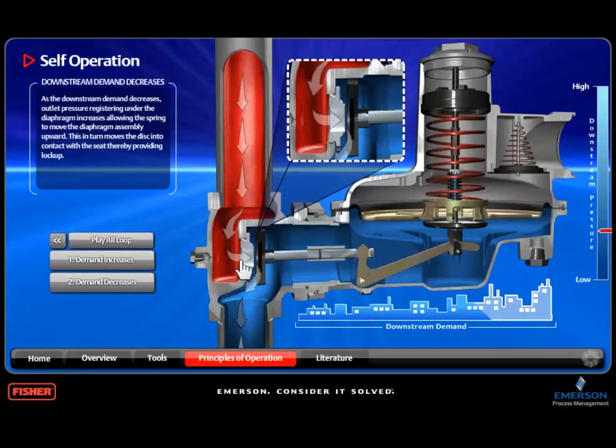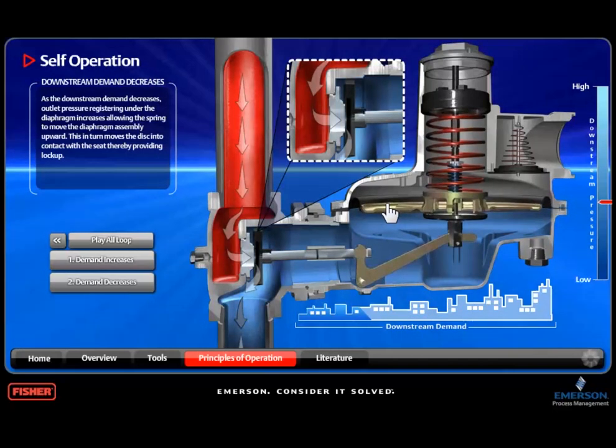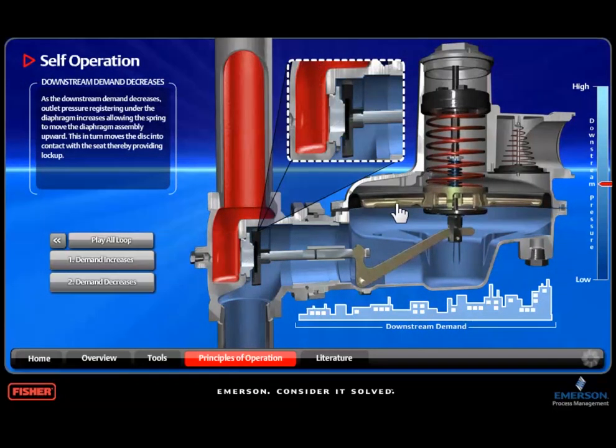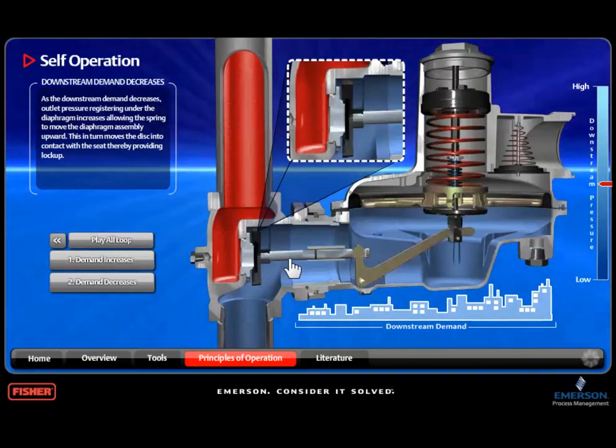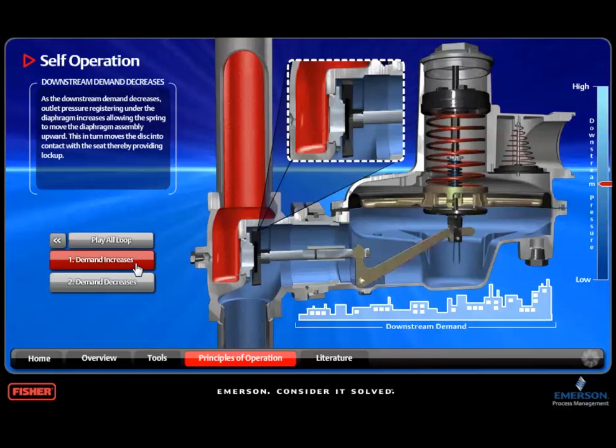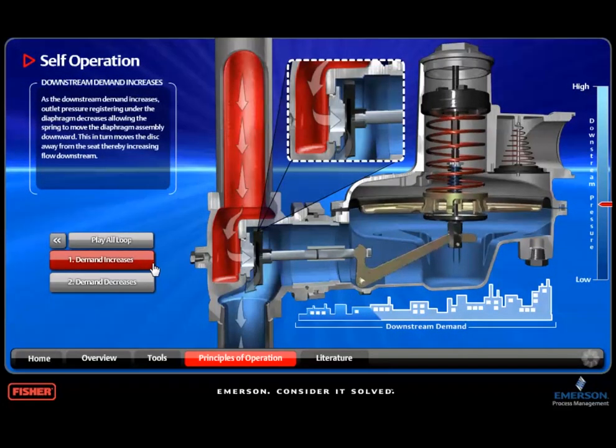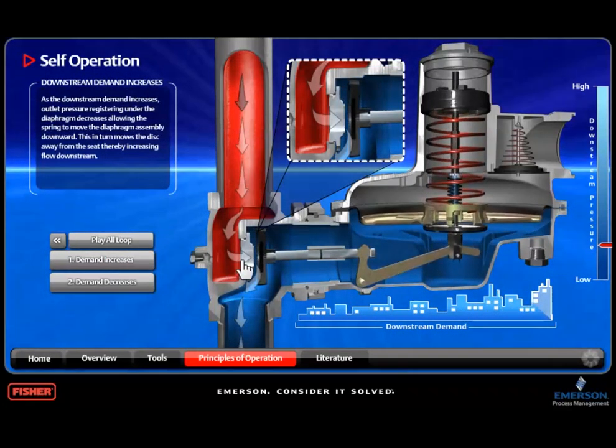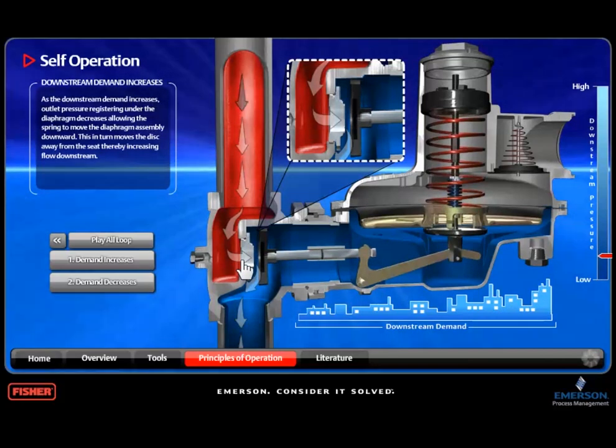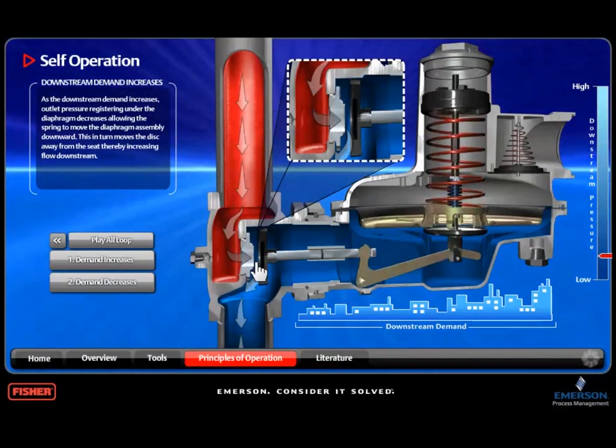The diaphragm will move upward if outlet pressure increases, which will move the valve disc closer to the orifice. The opposite will happen if outlet pressure decreases. As outlet pressure decreases, the diaphragm moves downward, pivoting the lever and pulling the valve disc to the right away from the orifice.